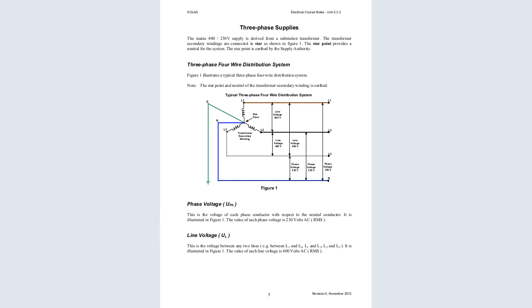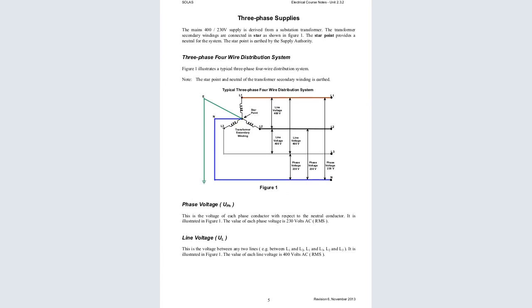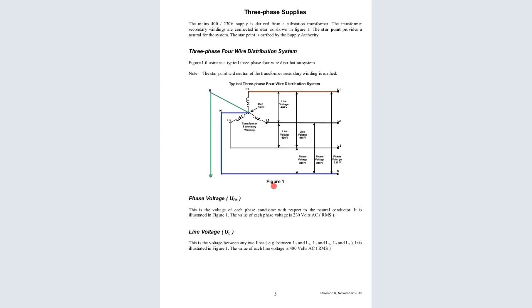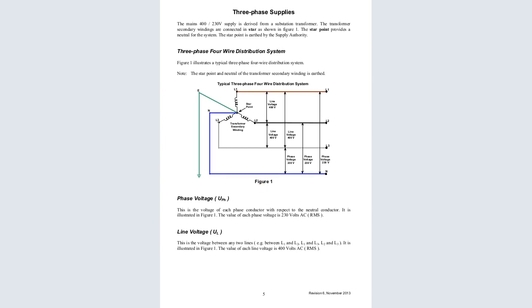Okay, let's continue. So the mains, which is always 400 for three phase and 230 for single phase supply, is derived from the substation or transformer. The transformer secondary windings are connected in star as shown in the figure. So the star point provides a neutral for the system. That is the most important part of the star, to provide a neutral to the system. The star point is earthed by the supply authority. So it is normally earthed by Kenya Power. Our supply authority in Kenya is the Kenya Power and Lighting Company.